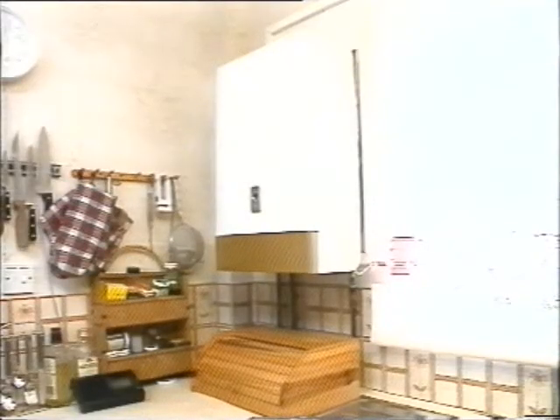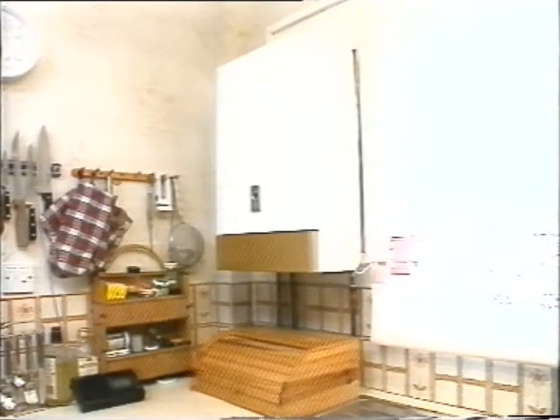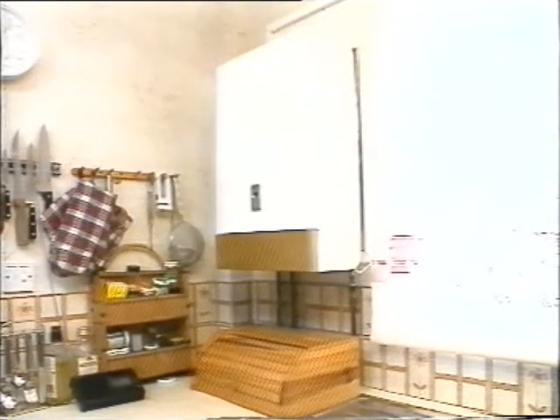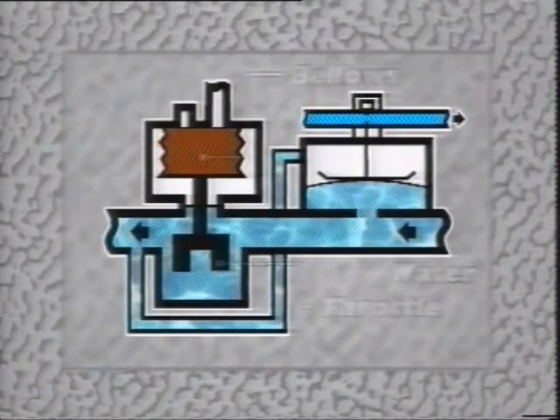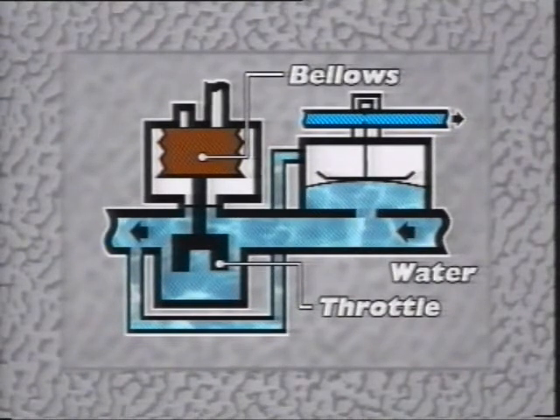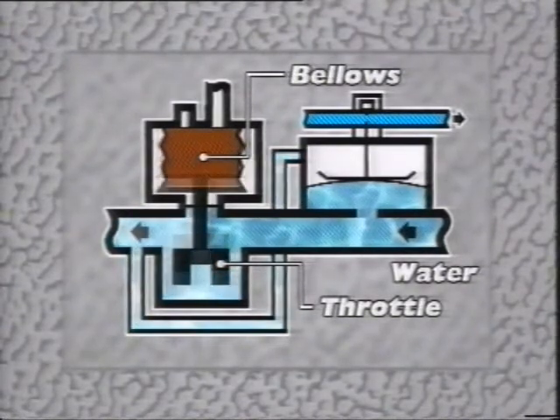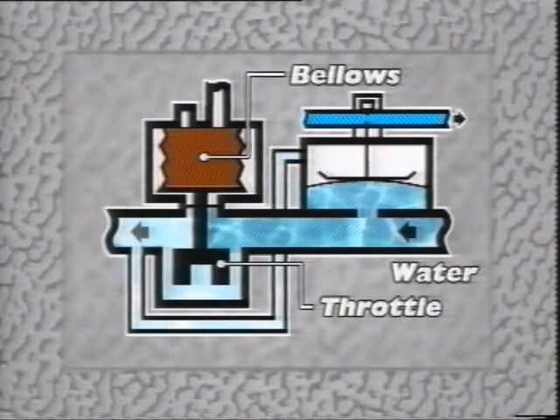This is a large instantaneous hot water heater. It delivers hot water to draw-off points throughout the property, so it's commonly known as a multi-point water heater. Heat input is usually greater than 12 kilowatts, so it needs to be flued. Normally, it's room-sealed. The temperature of the outlet is controlled by a vapor pressure thermostat, and there's a cylindrical throttle which restricts the water flow in the heater. As the bellows move, they reduce the flow, and with less water to heat, its temperature rises, and so the outlet water is hotter.